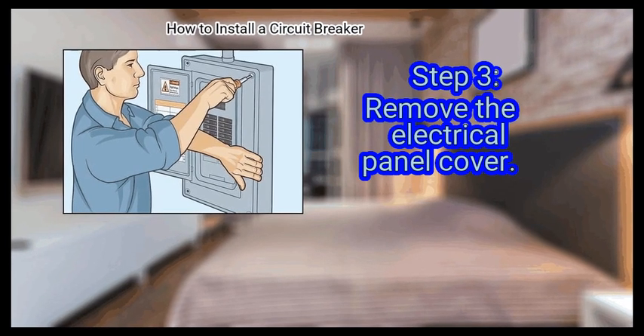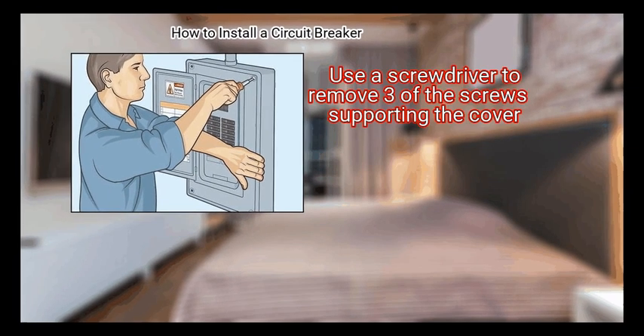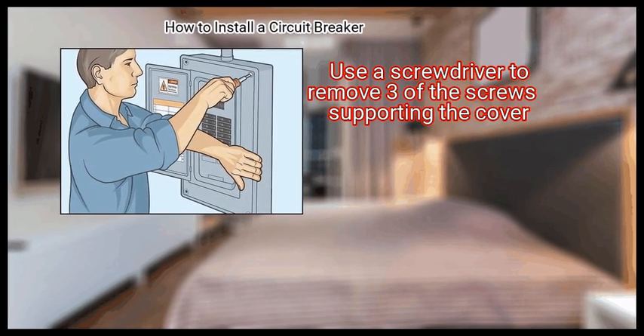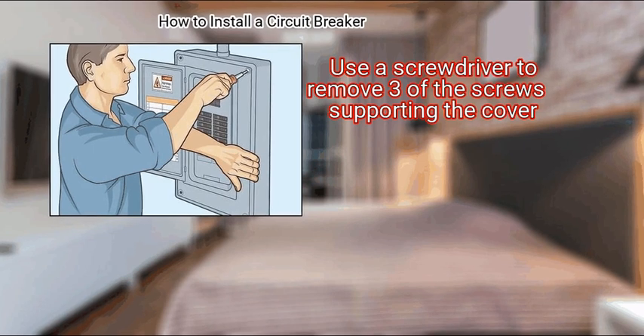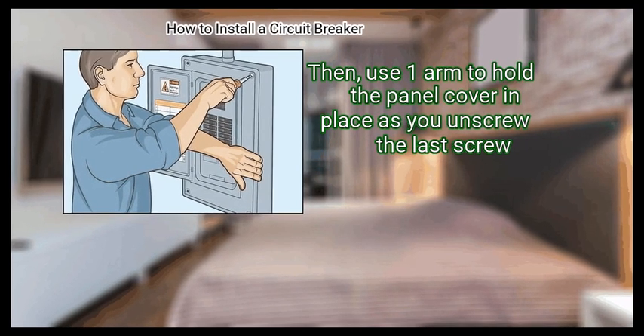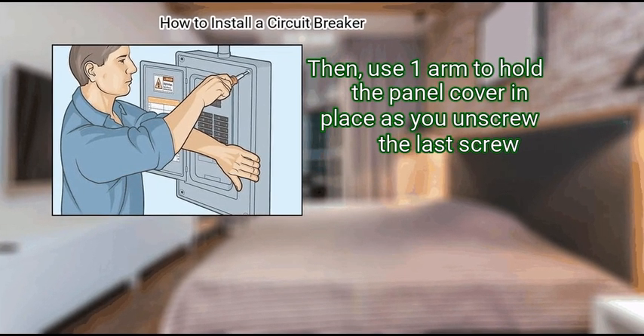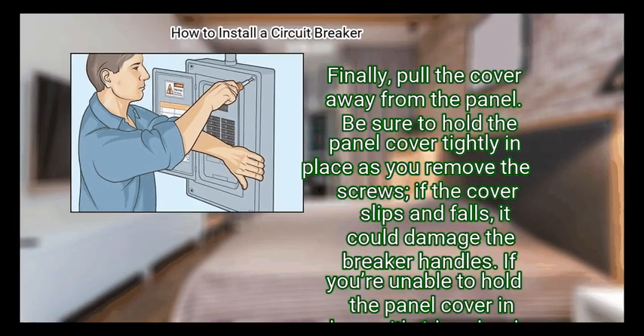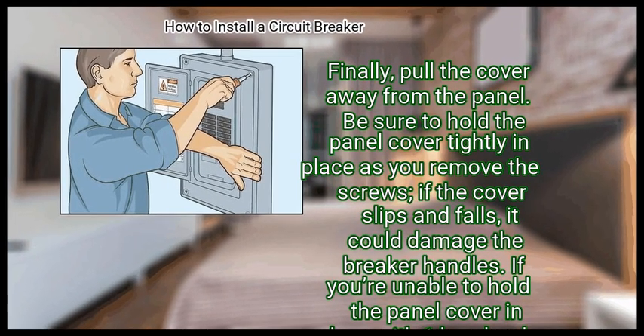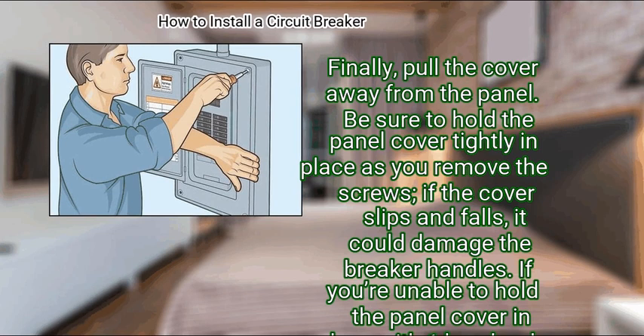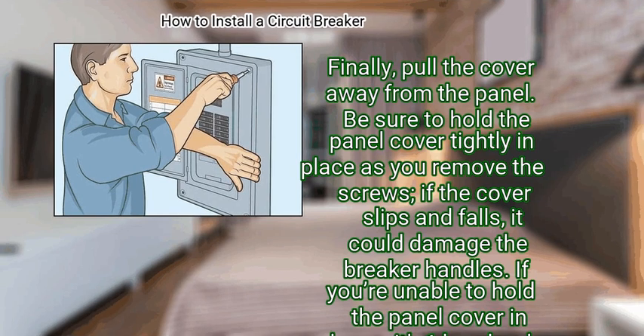Step 3. Remove the electrical panel cover. Use a screwdriver to remove three of the screws supporting the cover. Then, use one arm to hold the panel cover in place as you unscrew the last screw. Finally, pull the cover away from the panel. Be sure to hold the panel cover tightly in place as you remove the screws. If the cover slips and falls, it could damage the breaker handles. If you're unable to hold the panel cover in place with one hand, ask a friend to help you.